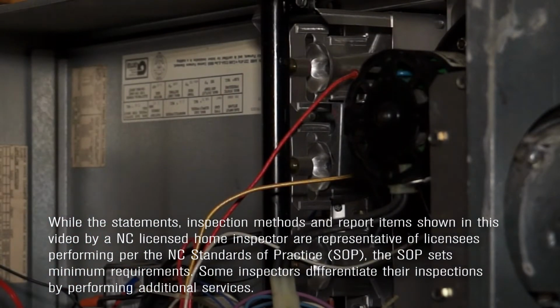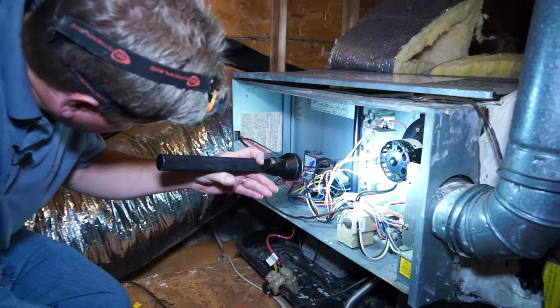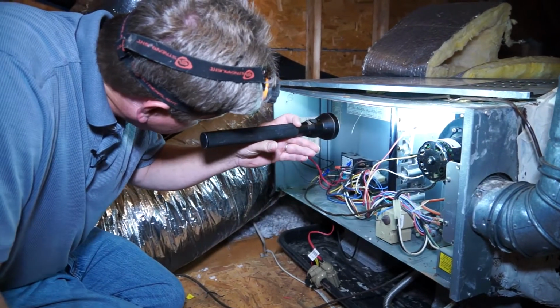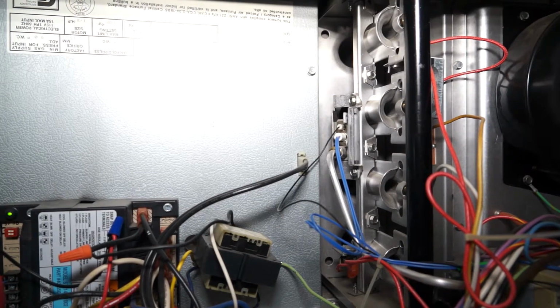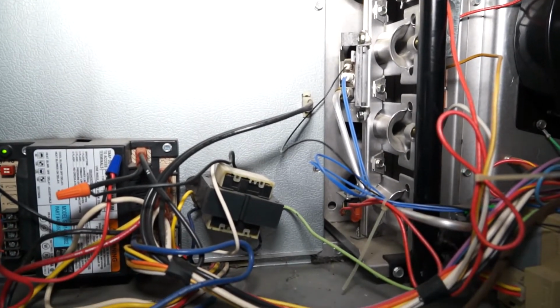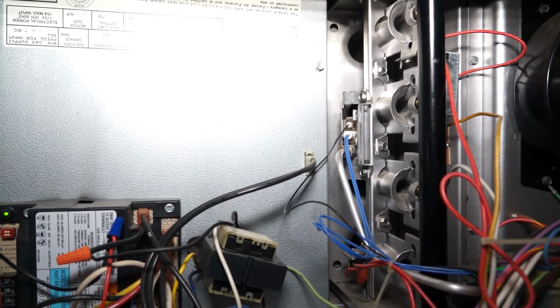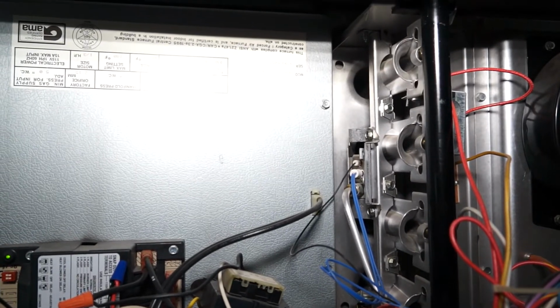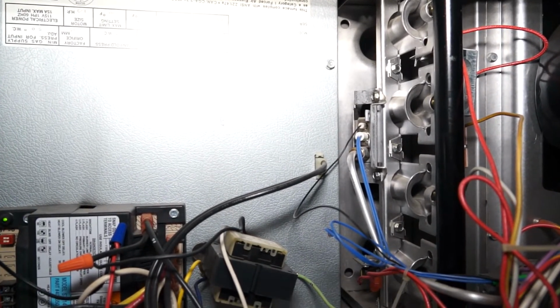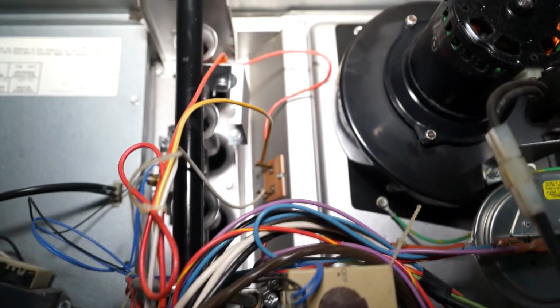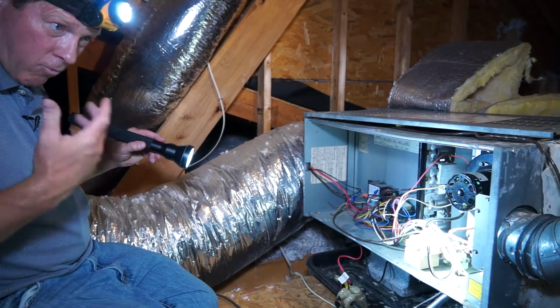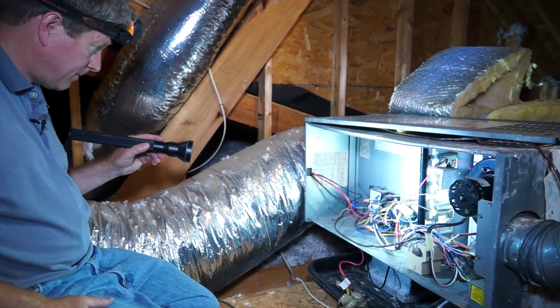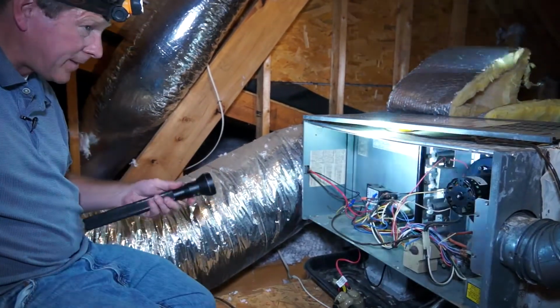In the case of the furnace, I'll remove the cover and inspect the inside of the unit. I don't have a sealed heat exchanger, so I can see down in it just a little bit. I'll look for signs of rust, check all my safety valves, check the exhaust blower for cracks and damage and other issues, and then of course I'll run it and monitor what the flame looks like and how it's operating.